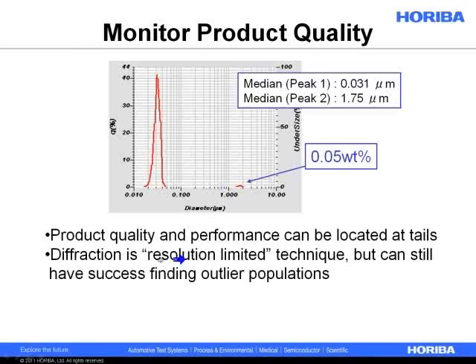Diffraction is resolution limited. If the first peak is at a median of 31 nanometers and you mixed in another material at a median of 40 nanometers, diffraction wouldn't be able to give you baseline resolution between them — it would most likely give you one peak that's a mix of the 30 and 40 nanometer material. It's not measuring every single particle; because it measures an ensemble of particles, you have limited resolution.